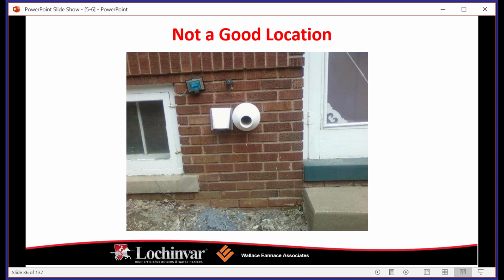So this is the aforementioned concentric kit. You can see that there is a cone with the tube right in the middle of it. The flue gases are coming out of the cone here, and we're pulling our combustion air in through the back of that bell-shaped thing. We have a better picture of this coming up in a few slides. So this is a great what-not-to-do. Let's figure out how many things are wrong with this picture in one shot.